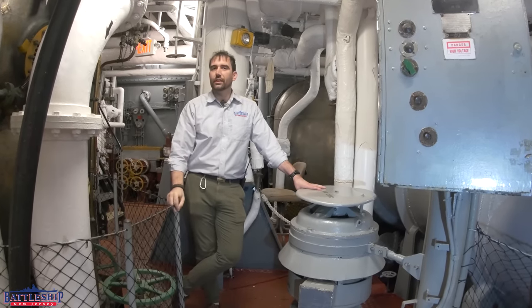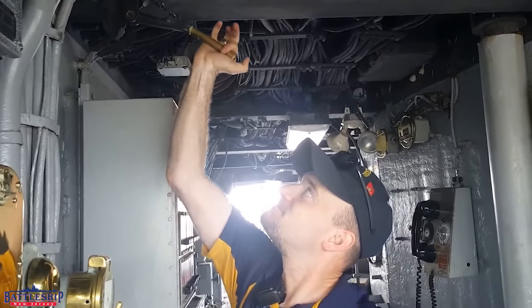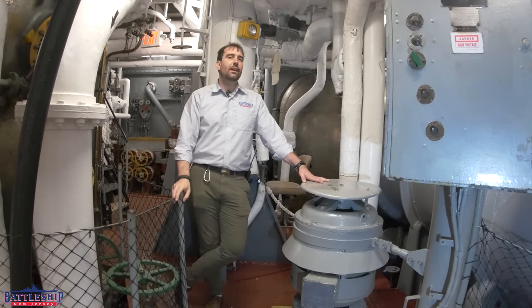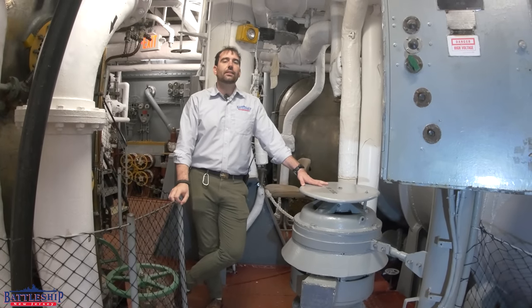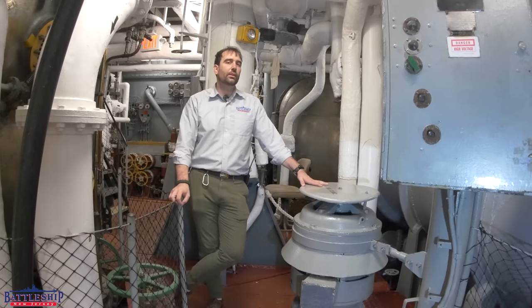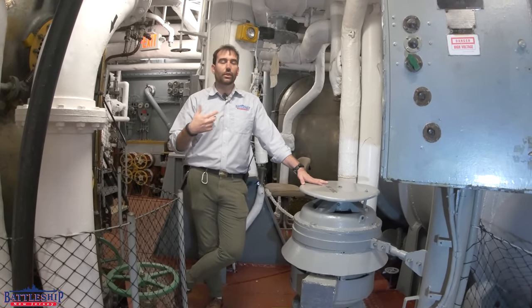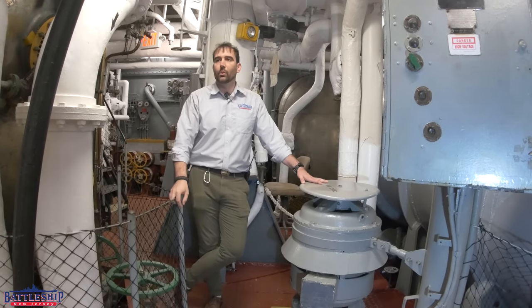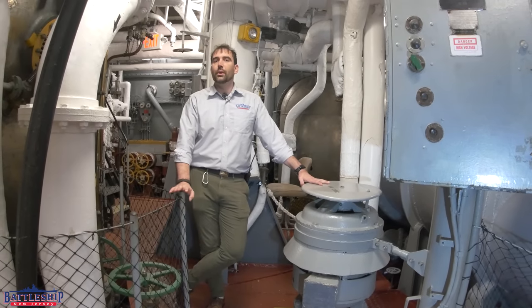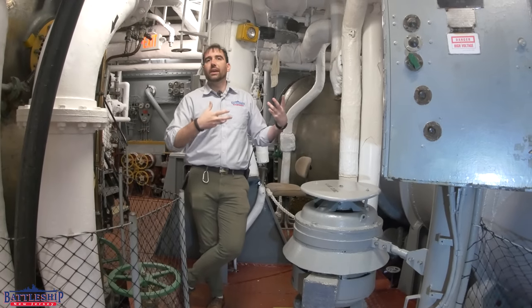Once it's feed water again, we use the main feed pumps to suck it out of the condenser and back into the deaerating feed tank, then send it into the boiler again to keep the steam cycle going — it's an almost perfect loop. However, whenever we blow the ship's whistle, blow down the tubes, or use the presses in laundry, we lose some steam. So the ship has three evaporators in other spaces making more boiler feed water, and there are tanks along the side of the ship forming part of the torpedo defense that hold make-up feed water. If we're doing more than eight knots, the ship scoops up all the water it needs; below eight knots, we have to use pumps to draw that water into the condensers.